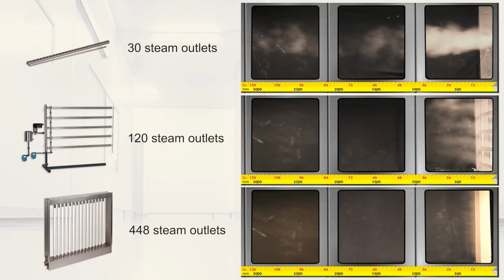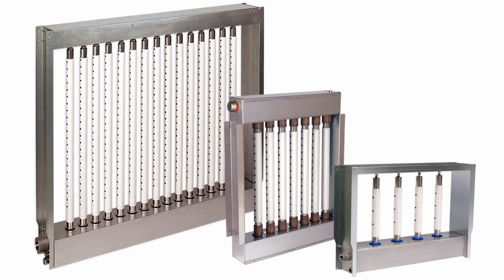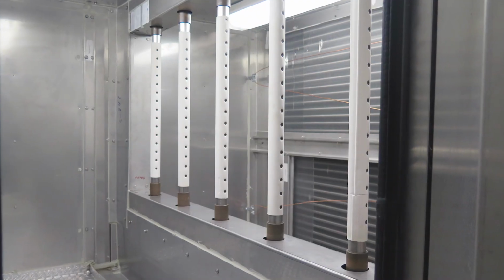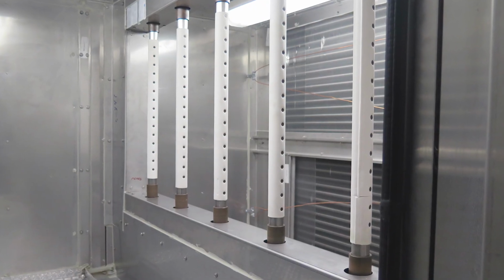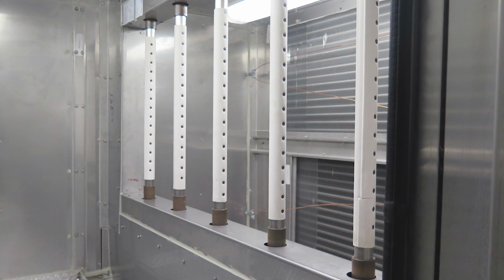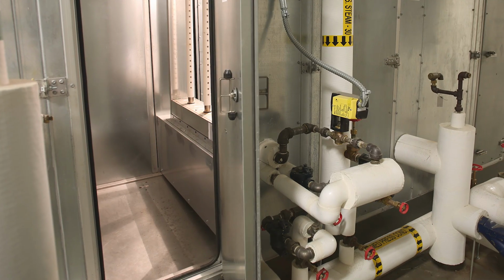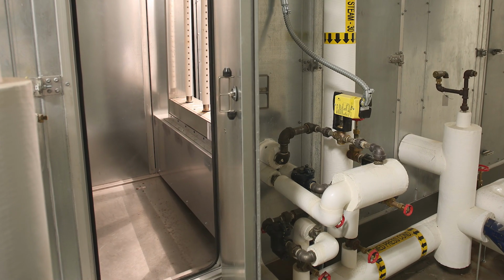Mm-hmm. Kind of going back to that bypass example, you want it to be in contact with as much of the air as possible. And having a complete assembly makes life easier, especially if you're going into an air handler. If it goes in like a coil with a frame already around it, it's already pre-built versus having to assemble on site. That can make life easier. Planning for how am I going to get the steam into it and how am I going to do a drain? Because there were some of those inefficiencies we talked about. We need to make sure we can remove that because you don't want it to make it into the airstream.